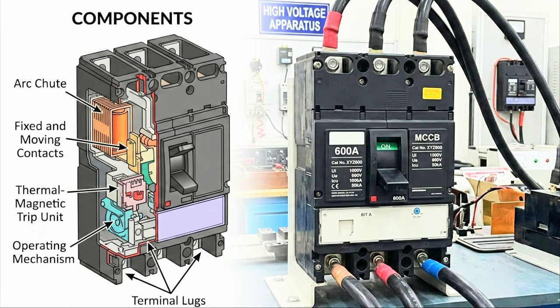Now, friends, you are looking on your screens at this 600 amps MCCB. It has a safety device called the under voltage relay, UVR. Many times I have a problem with that MCCB continuously tripping or not closing the breaker. That's why our equipment is not working, or the equipment that requires the supply does not get it.